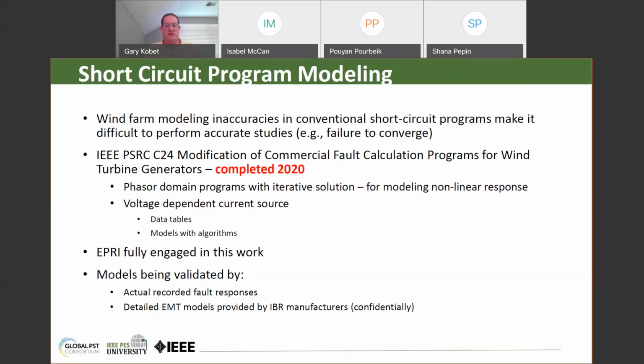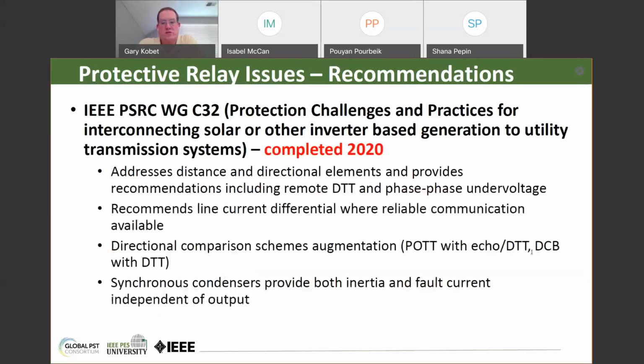Another IEEE Power System Relay Committee group, which the next slide shows, was Working Group C32. This report was also completed last year and is available on the Power System Relay Committee website. It addresses the things that we talked about here regarding distance and directional element sensitivities, and provides recommendations, including the use of direct transfer trip from strong sources to IBR sites, and also the use of phase-to-phase undervoltage to go along with distance and directional element schemes. Line current differential, of course, as we said a minute ago, is an excellent scheme typically in these kinds of systems.